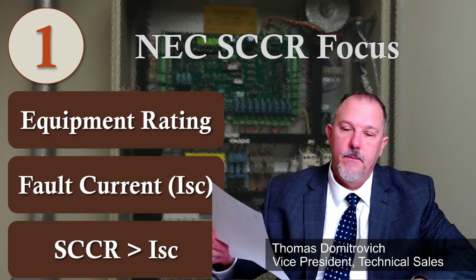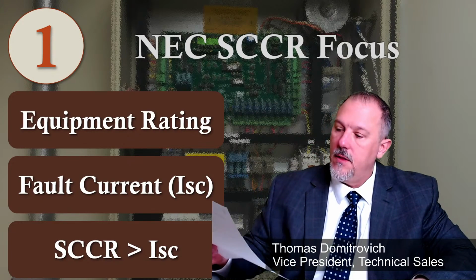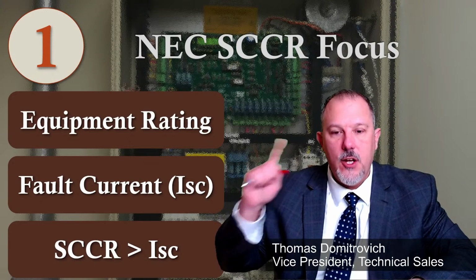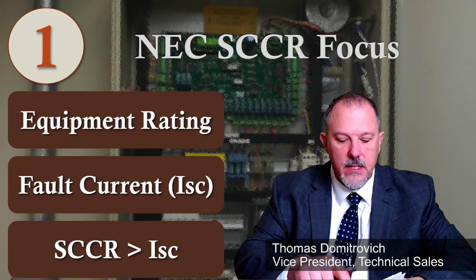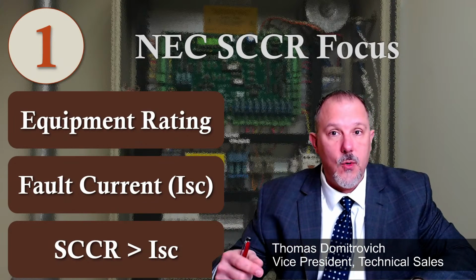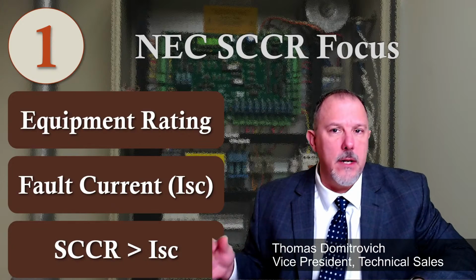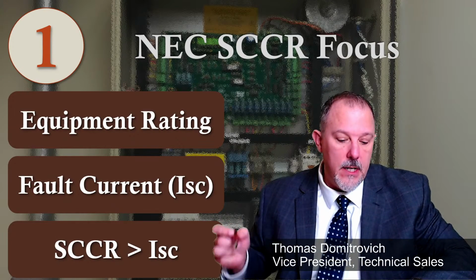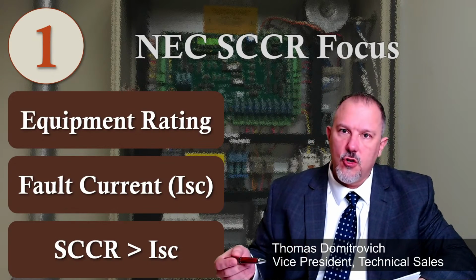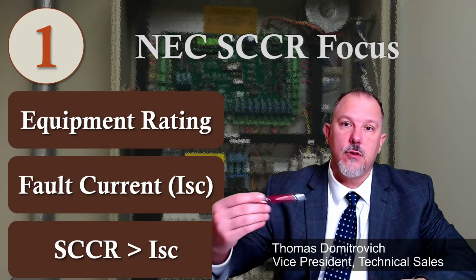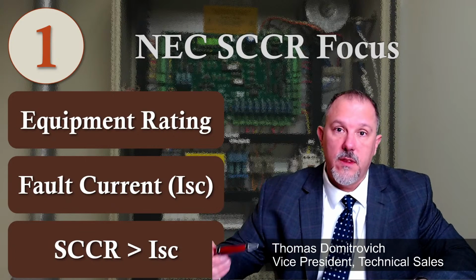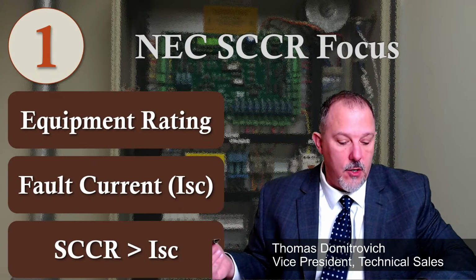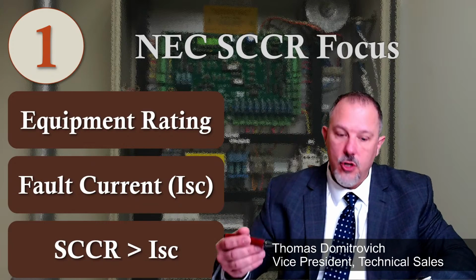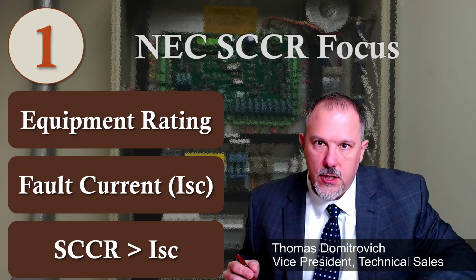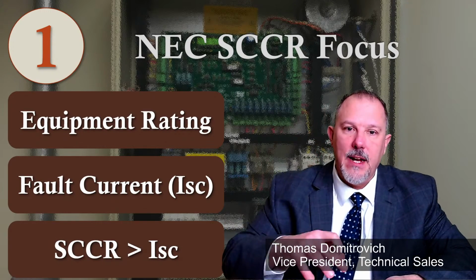Now, in my article that is associated with this Tech Tuesday, whatever you want to call it, I put all of the section numbers that are associated with each of these. Equipment ratings, it's marking of SCCR on equipment. That's mandatory. And a lot of times, if you're listing the product to a standard, you're going to cover that already. 409 is your industrial control panels. It tells you that you need to have an industrial control panel that is marked with the short circuit current rating on the equipment. Motor controllers, motor control centers, air conditioning and refrigeration equipment. This all talks about rating.